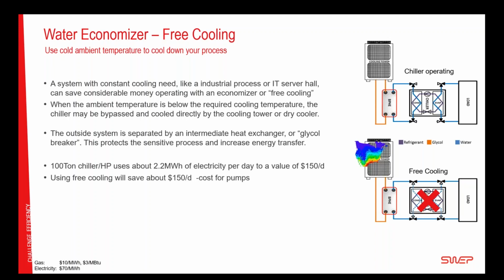So we say again, a 100-ton chiller, as we saw before, consumes 2.2 megawatt hours per day, about $150. And since this process requires cooling all year round, so this is 24/7, 365, if you're able to turn it off, you will save that $150 a day. Of course, not fully, because you still have to have pumps running and other things. But it's going to be, you know, minimum 90% of the operation cost is going to be for free.